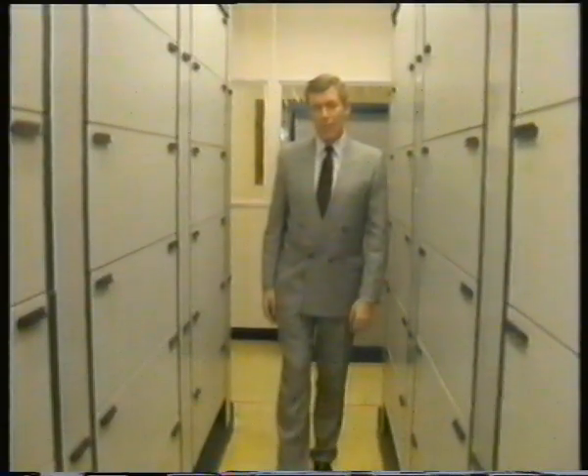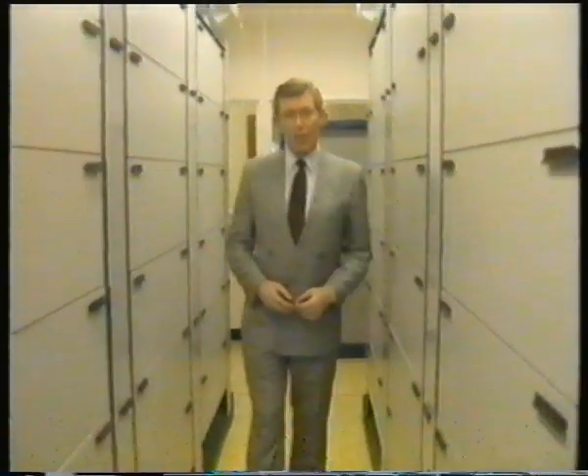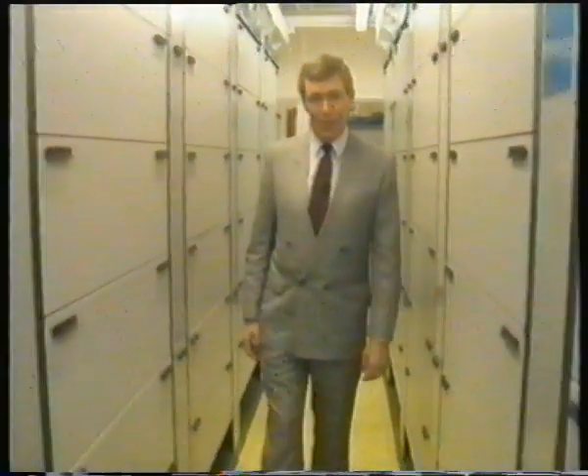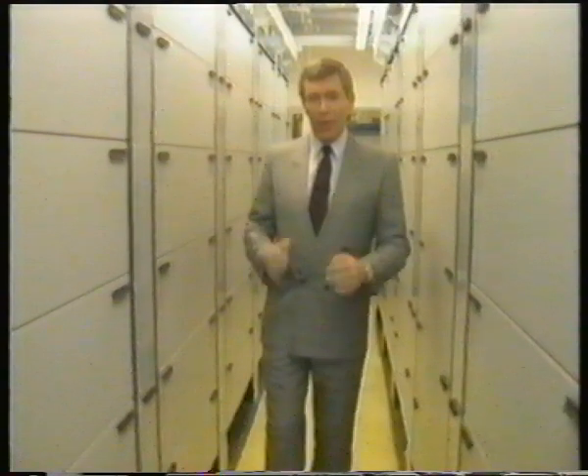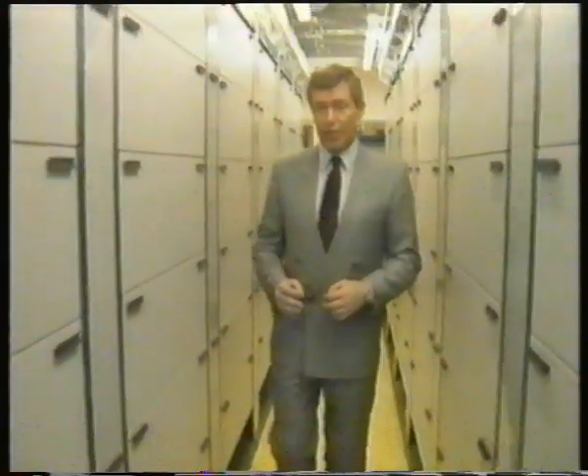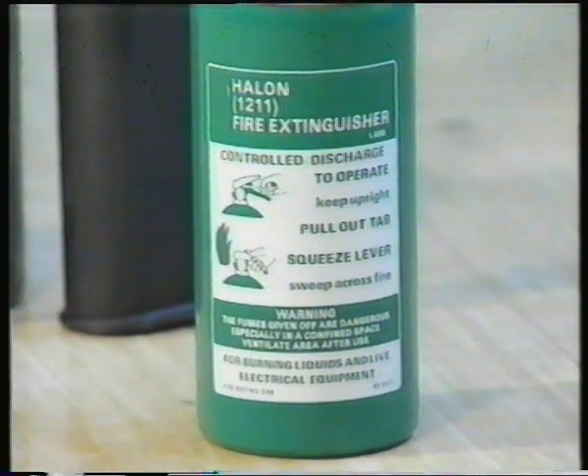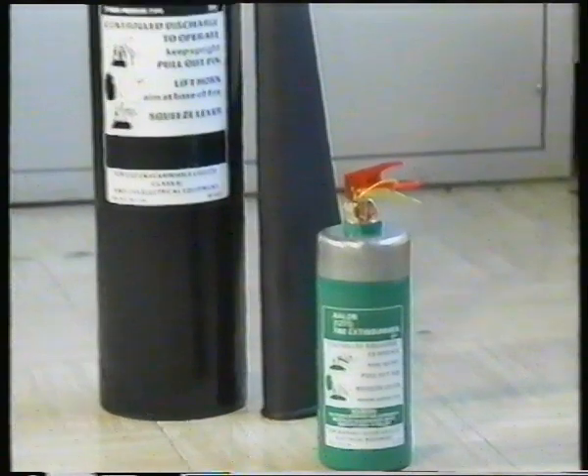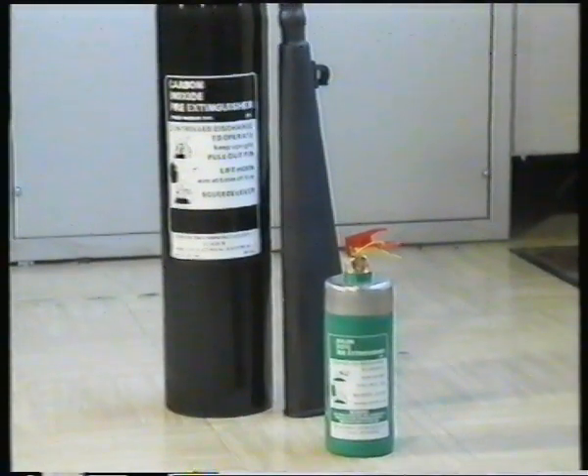I started off by saying how vital telephone exchanges are to the community, and that a fire could seriously disrupt that service. However, the incorrect selection of an extinguishing agent can be just as bad. Fires located around equipment areas should, if possible, be fought using clean agents such as halon 1211 BCF or CO2. Water, dry agents or foam will physically damage the equipment and interrupt communications.